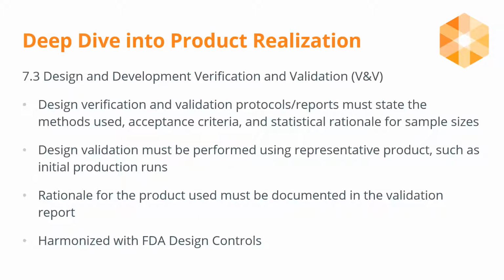Design verification and validation protocols and reports must state the methods used, acceptance criteria, and statistical rationale for sample sizes. Validation must be completed using representative product. The validation report should include a rationale for the product used. This is consistent with FDA design controls.